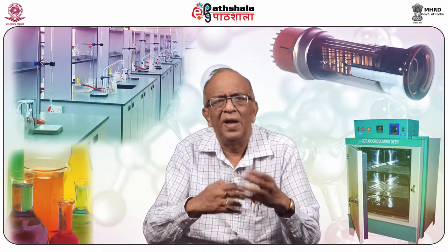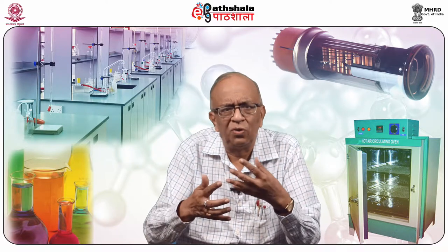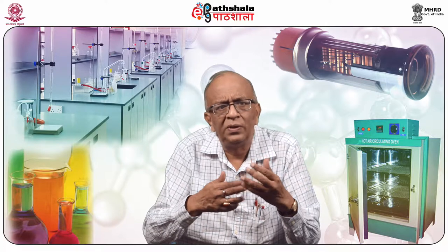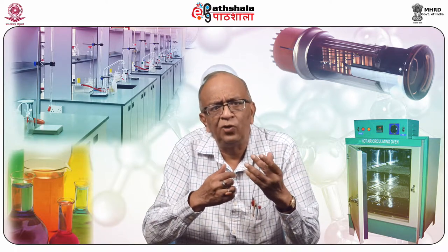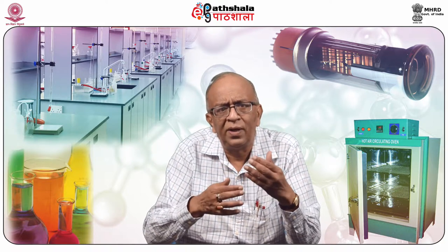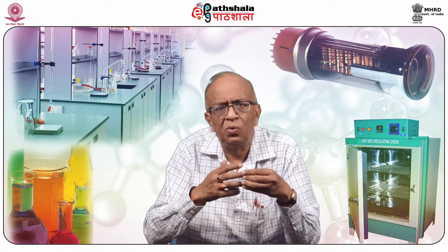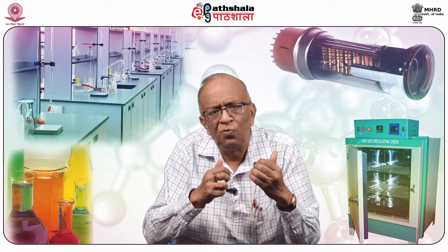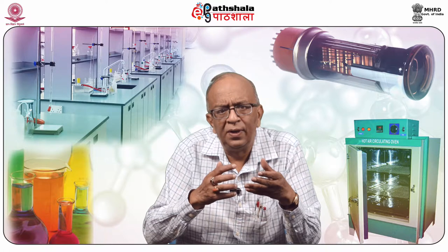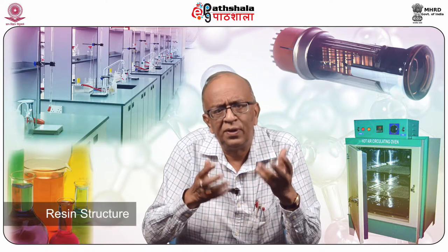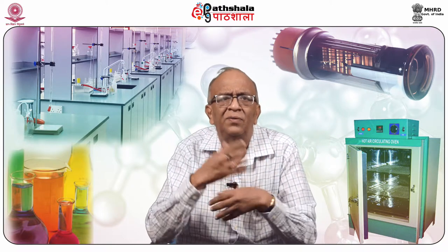Another important property of ion exchangers — whether cation or anion exchangers — is swelling. On taking up molecules of water, the resin swells. The high proportion of polar groups within the resin gives it a hygroscopic character. In a sulfonate resin, one can consider that the SO₃⁻ and H⁺ ions dissolve in the adsorbed water, yielding a solution of high concentration. Since the ions cannot diffuse out, there is a tendency for water to diffuse in to equalize the concentration. The amount of water that can diffuse in is restricted by the space available in the interstices of the resin structure, and in this way swelling facilitates the exchange of cations or anions.